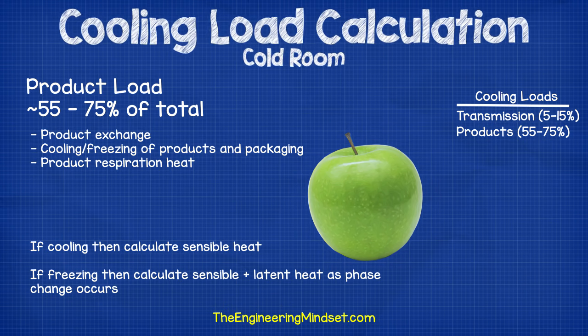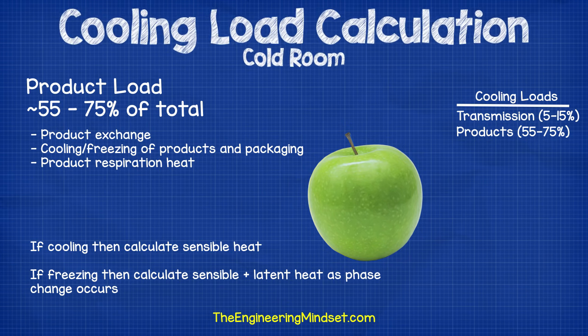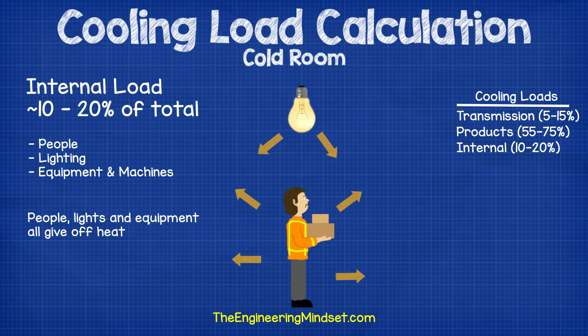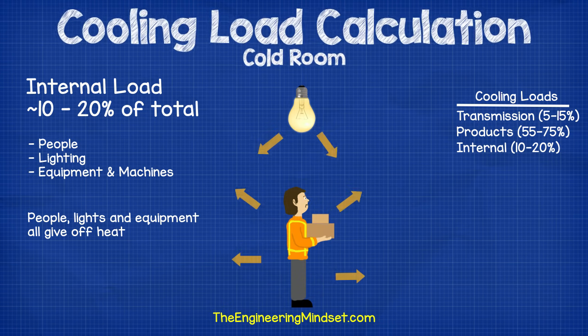You also need to account for the packaging as this will inherently be cooled also. Lastly, if you're cooling fruit and vegetables then these products are alive and they will generate some heat, so you need to account for the removal of this also. The next thing to consider is the internal loads which account for around 10 to 20 percent. This is the heat given off by people working in the cold room as well as the lighting and equipment such as forklift trucks.